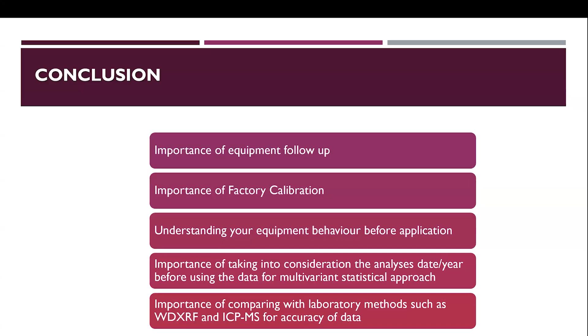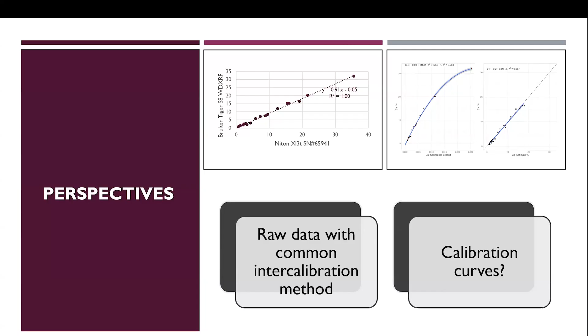Now, the next step for the network, which has ended, is to discuss how to proceed with the data processing to intercompare data coming from different analyzers with a common method. Which common method should be applied here? Should we use calibration curves, like the slope and intercept, to correct our data? Or should we just publish the raw data and propose a common method to intercalibrate the results? And should these data be quantitative? Or should we go further and use other physical characteristics of the instrument itself, like the spectral calibration element by element, which is what we're trying to do now with Michaela and Lee and Nadia.